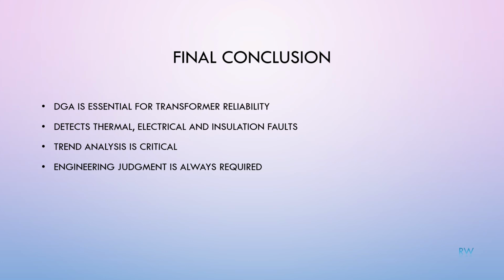Dissolved gas analysis is a powerful and essential tool for transformer condition monitoring. It helps detect thermal faults, electrical discharges, and insulation degradation at an early stage. Trend analysis and correct interpretation are critical. When used properly, DGA significantly improves transformer reliability and operational safety.